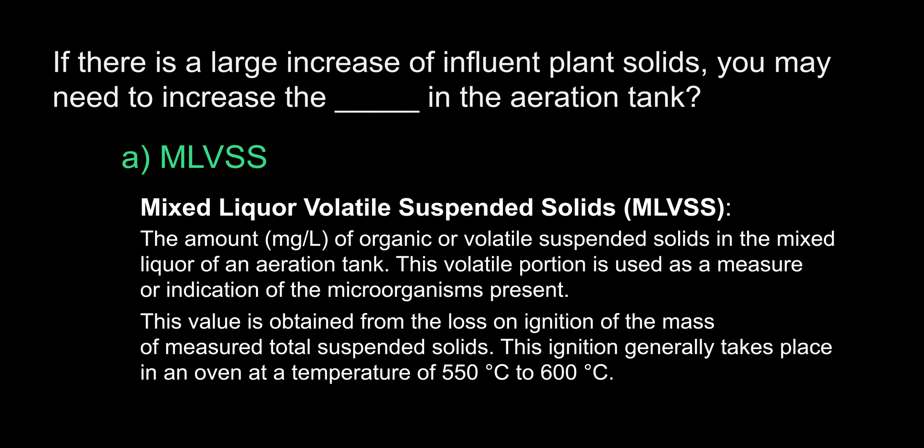Generally speaking, if a larger than normal amount of solids are arriving at your plant, there will be more food for the bugs. If there is going to be more food for the bugs, it is going to be important to keep the food-to-mass ratio balanced appropriately. More food means you're going to want more bugs in your system to eat it all up. This is most easily achieved by decreasing your wasting rates, which increases your mixed liquor suspended solids (MLSS), and when you increase your MLSS, you are also increasing your mixed liquor volatile suspended solids (MLVSS).